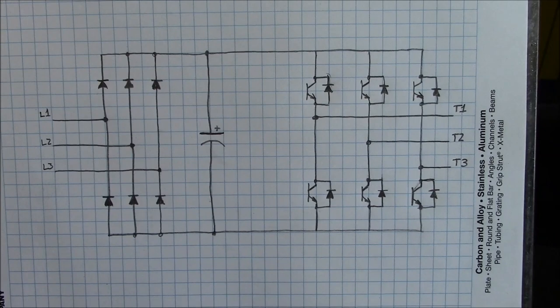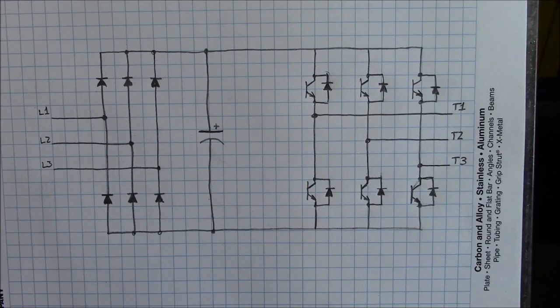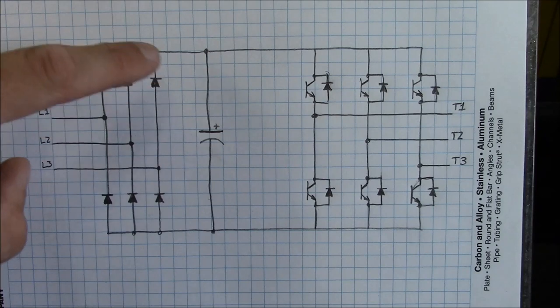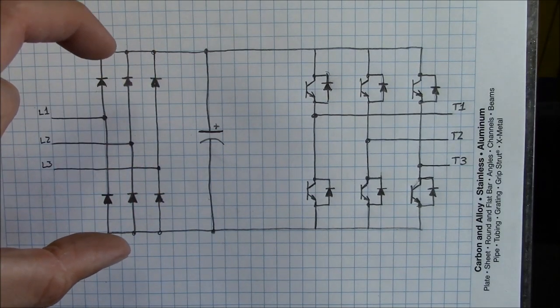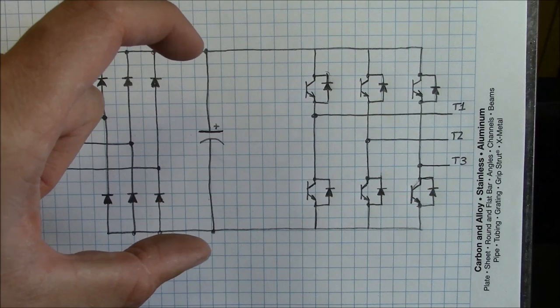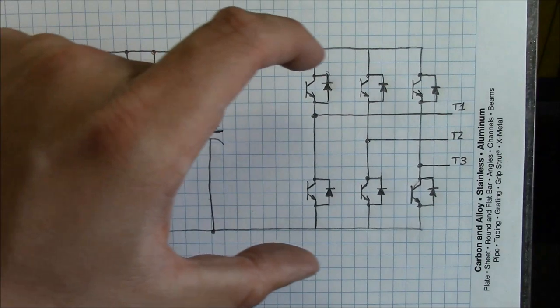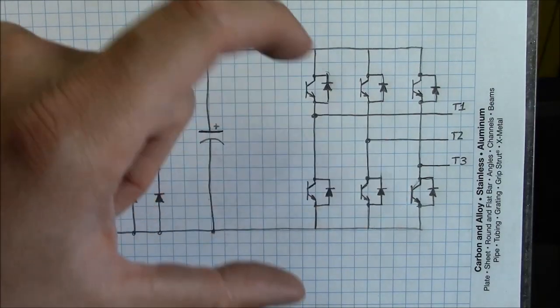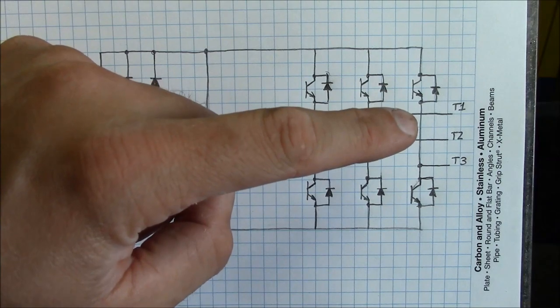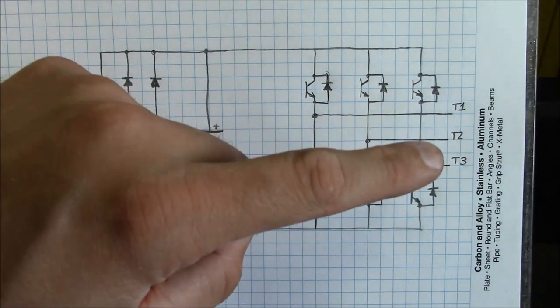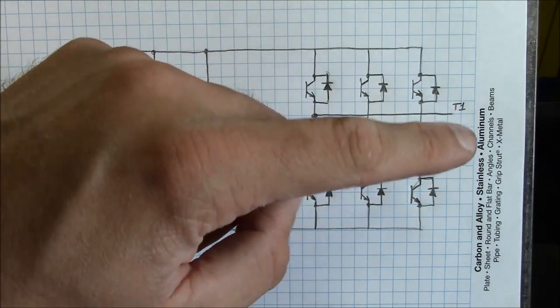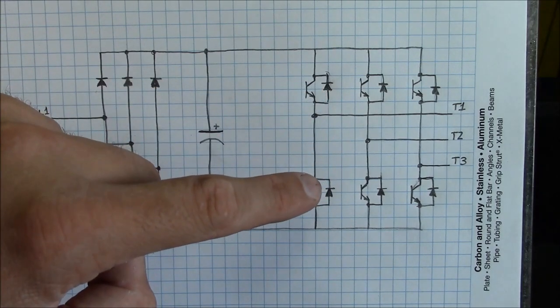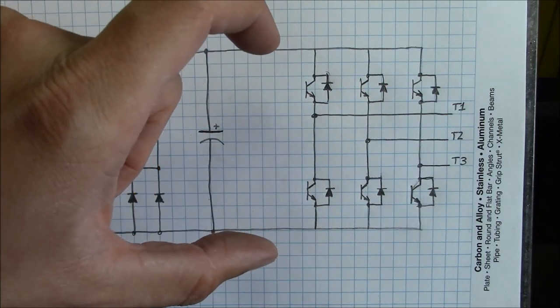Okay, this is a super simplified schematic of how a VFD or a servo drive or really any kind of motor drive works. Basically the way they work is AC power comes in here and it gets rectified here in this section into DC power, and then on these lines here that's what's called the DC bus. The DC bus gets filtered by this great big capacitor right here, and then it's fed down here into the drive section. These are transistor modules here that take the DC power and invert it back into three-phase AC power, an approximated version of AC, and send it out to the motor. And then when the motor decelerates it acts like a generator and it creates excess electricity that gets fed back into this inverter section, and then it gets basically rectified the opposite way and fed back into the DC bus.